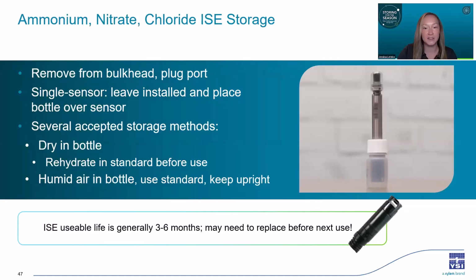And again, use the standard closest to your measurement range. That way, if it does tip over and submerge the membrane, it's really not going to be a big deal and it's not going to damage it. Since the ISE usable life is generally about 3 to 6 months, you'll likely need to replace the sensor and the sensor tip before using it again.